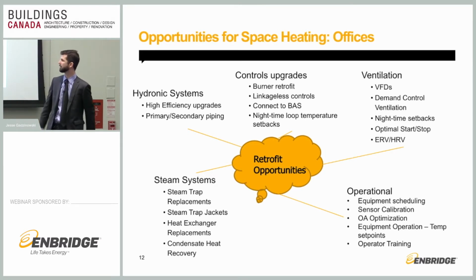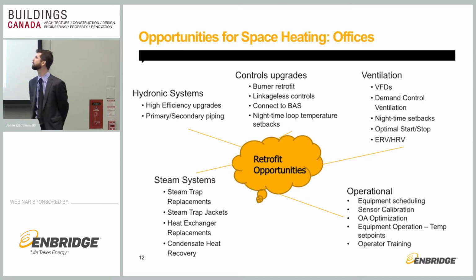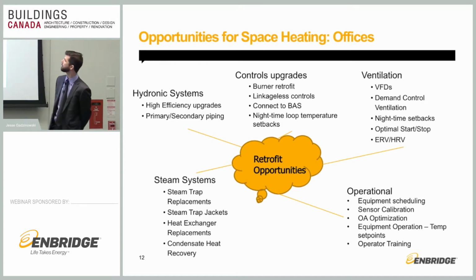Condensate heat recovery, again, putting that into domestic hot water. So controls upgrades, we're looking at burner retrofits, going from a single stage or a two-stage burner to a modulating burner. Simple control upgrade can save a substantial amount of gas. Linkageless controls for steam and hydronic boilers, getting a more digitized output for your air-to-fuel ratio. It's a good opportunity to save gas as well.